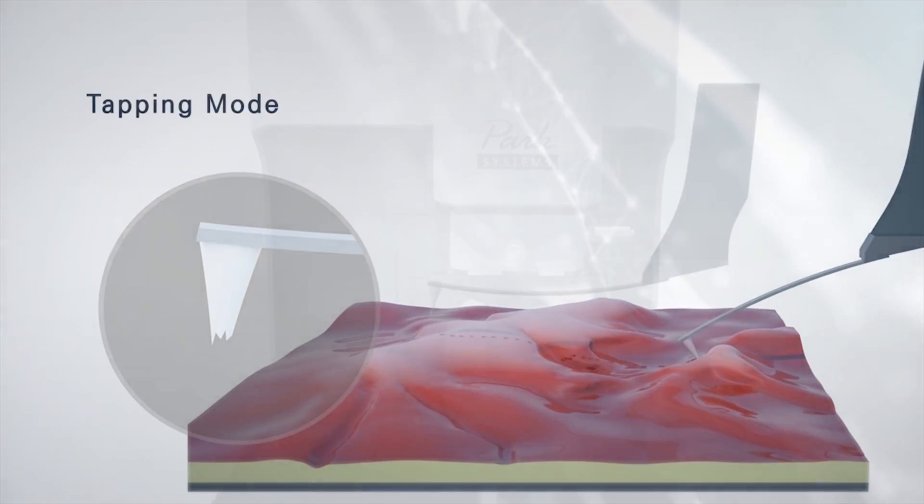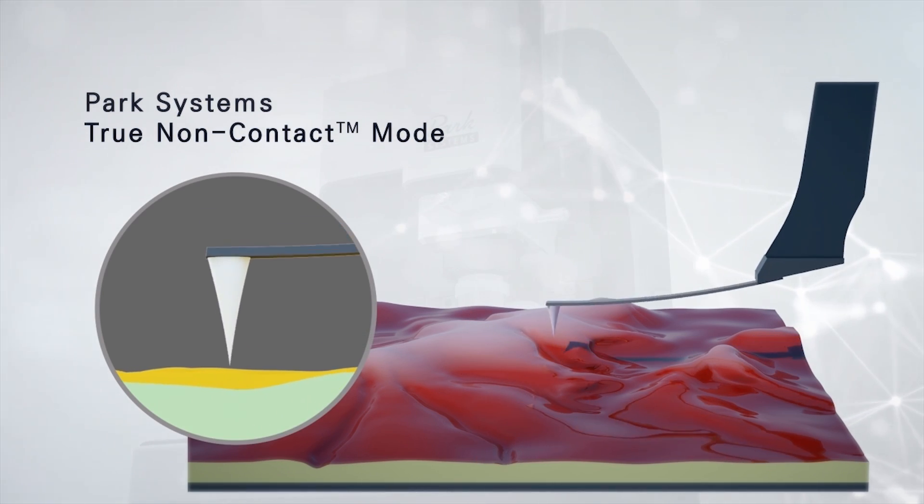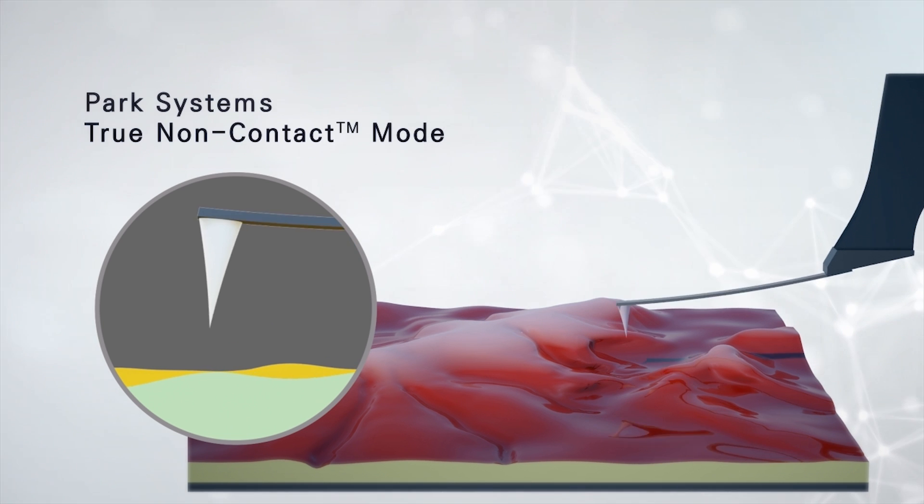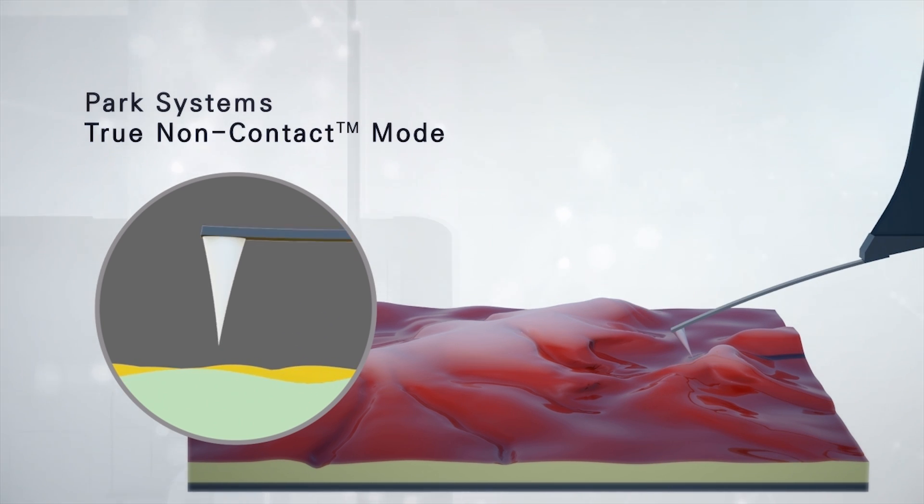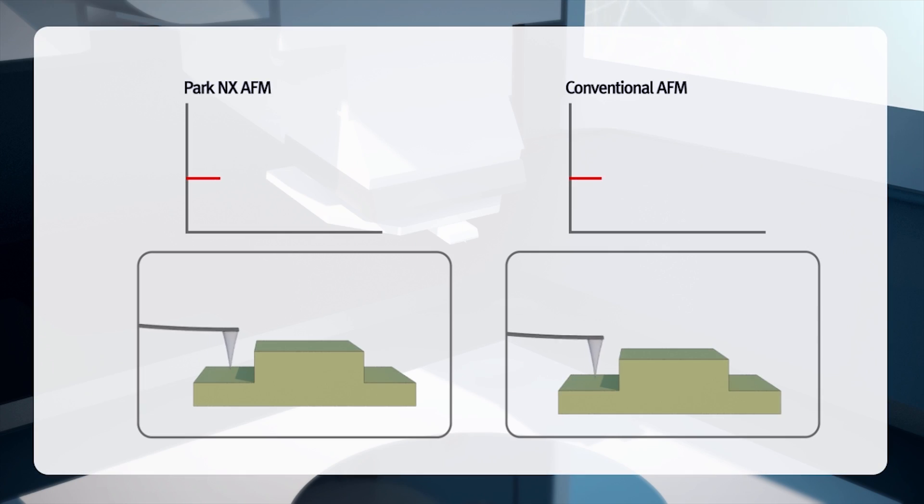However, AFM measurements with Park Systems' true non-contact mode involves no contact between the tip and sample, thus no sample damage and almost no tip blunting, enabling accurate measurement over many scans and greatly lowering related tool upkeep costs. In addition, with the development of a high-performance Z detector which effectively reduces noise, sample surface details smaller than a nanometer can be accurately measured without any creep effects at feature edges.